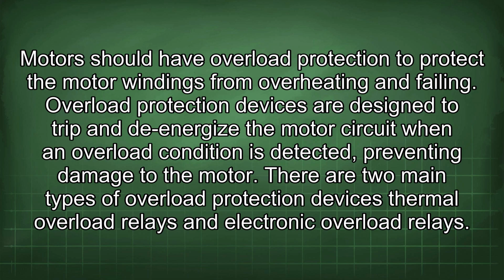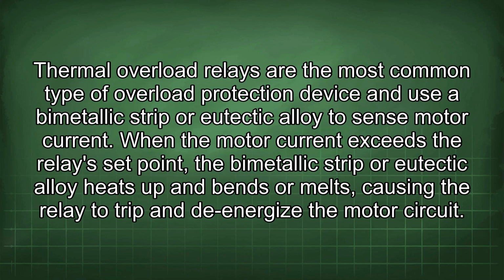Motors should have overload protection to protect the motor windings from overheating and failing. Overload protection devices are designed to trip and de-energize the motor circuit when an overload condition is detected, preventing damage to the motor. There are two main types of overload protection devices: thermal overload relays and electronic overload relays. Thermal overload relays are the most common type of overload protection device and use a bimetallic strip or eutectic alloy to sense motor current. When the motor current exceeds the relay set point, the bimetallic strip or eutectic alloy heats up and bends or melts, causing the relay to trip and de-energize the motor circuit.